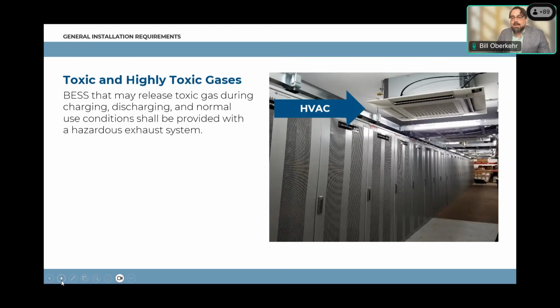On to toxic and highly toxic gases. This is again primarily indoor, inside walk-in units. Lithium ion doesn't release any toxic gases during normal charge and discharge operations, and therefore is not required to ventilate, which we'll get into later. Some batteries that are not lithium ion may release toxic gases during normal charging and discharging. Those are regulated by the code separately, as I'll get into later. Forced fan systems used in battery charging rooms and other areas where gases can build up are required in some instances, and best practice in others. We'll cover that more later.